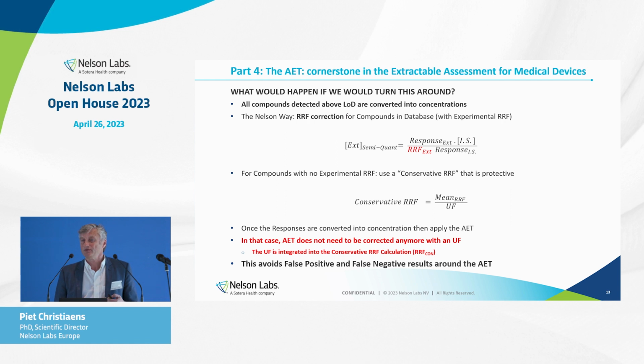There you could say, okay, we will introduce a default RRF value, including the uncertainty factor of the statistics of your database. And that's the formula: the mean of the RRF of the population divided by the uncertainty factor. That is okay, but you don't need to bring your AET level down anymore then, because otherwise you do it twice. You bring your AET level down with an uncertainty factor, and you would bring your concentrations up with an uncertainty factor, which is double dipping. You know, it is correcting twice, so that is not necessary anymore.